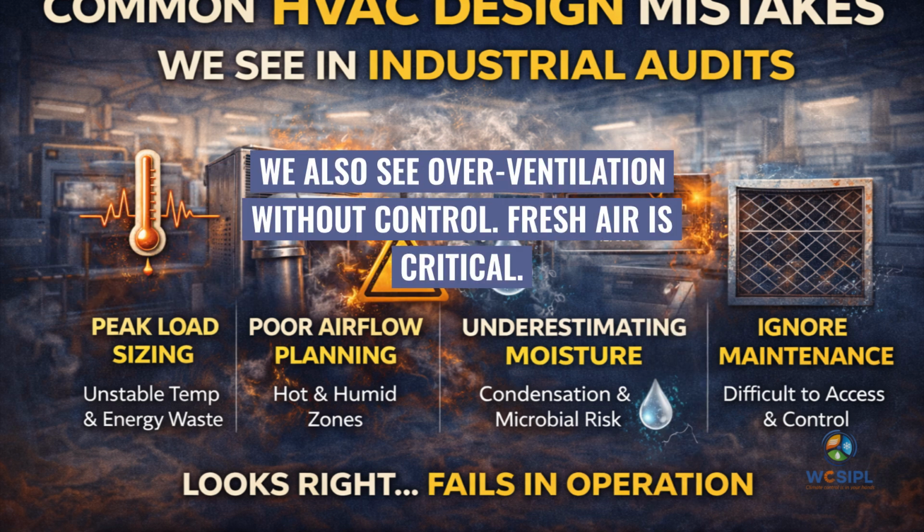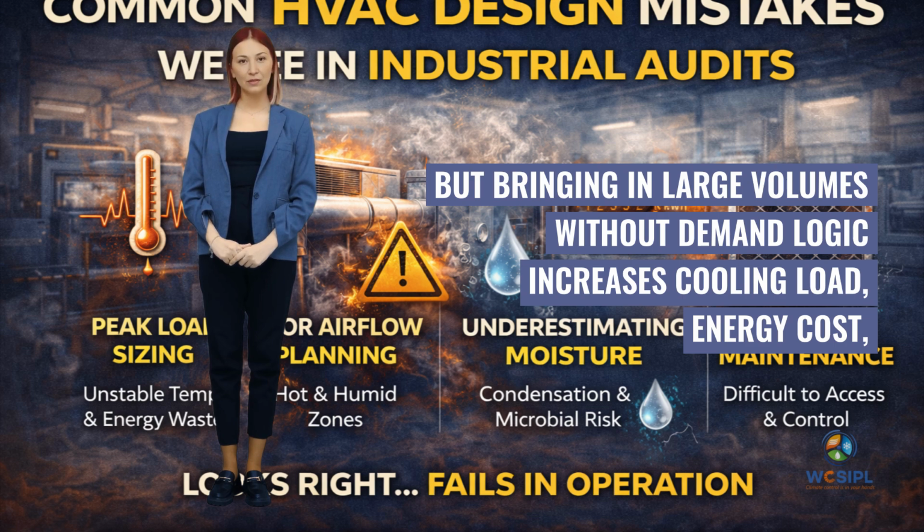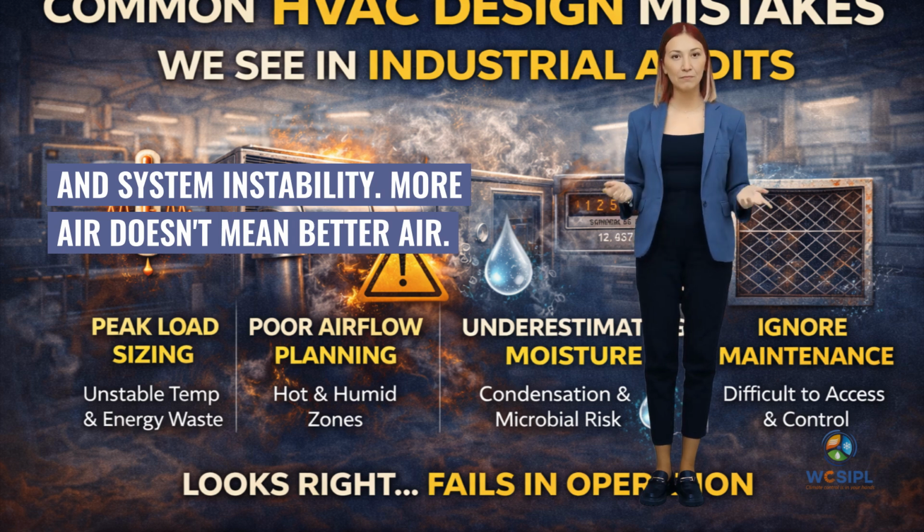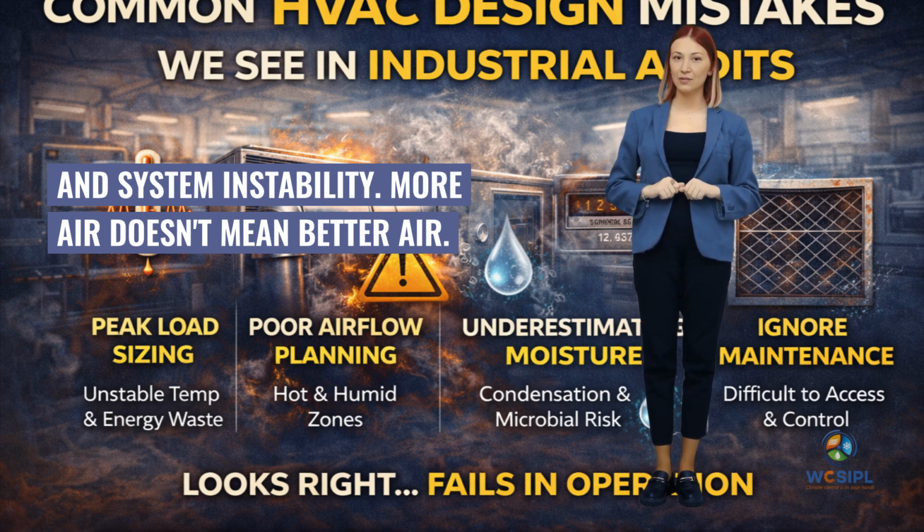We also see overventilation without control. Fresh air is critical, but bringing in large volumes without demand logic increases cooling load, energy cost, and system instability. More air doesn't mean better air.